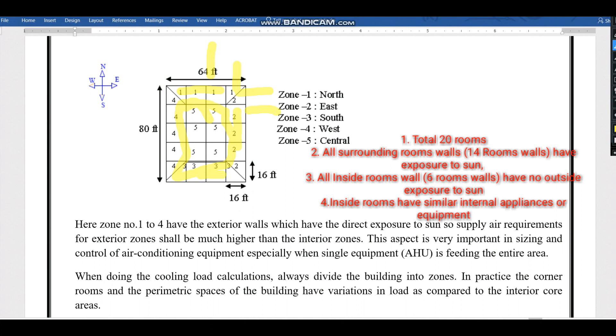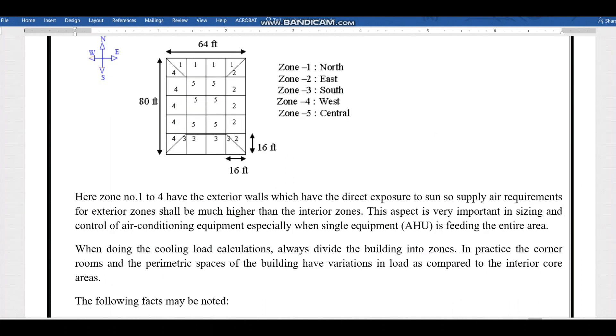The interior walls with no direct sun exposure form Zone 5 — the central area. Zones 1 through 4 have exterior walls with direct sun exposure, so the supply air requirements for exterior zones will be higher compared to interior zones. In cooling load calculations, always divide the building into zones, as corner and perimeter spaces have varying loads compared to interior core areas.